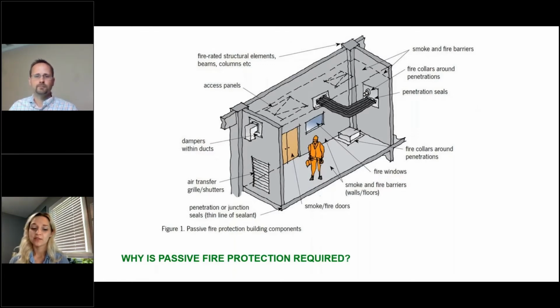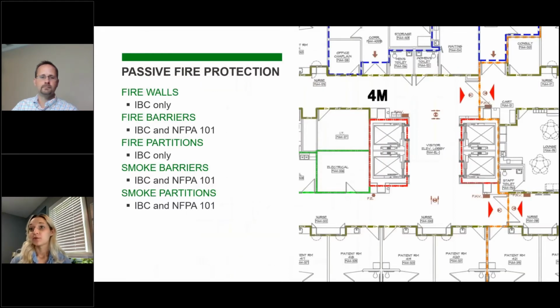So really, what is passive protection? If we think about fire protection in general, we think about active systems that react to a fire, like alarms and sprinklers. But passive protection is equally important, and it's all of the things that don't necessarily directly react, but that maintain sturdiness and separation with rated walls and ceilings, structure, and then all of the openings that are being protected in those assemblies, like rated doors and dampers. So it's incredibly important that we understand the types of passive protection and how our systems can interact with them, and how we protect them, specifically with dampers.